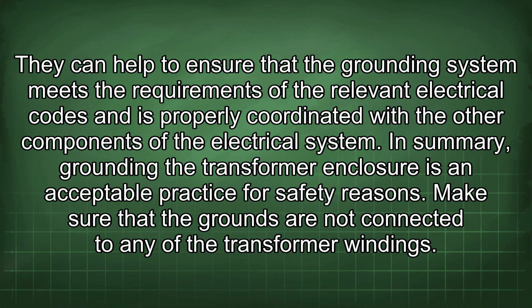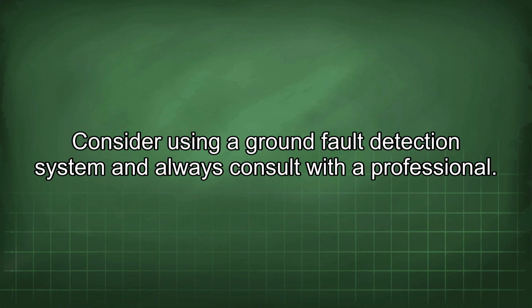In summary, grounding the transformer enclosure is an acceptable practice for safety reasons. Make sure that the grounds are not connected to any of the transformer windings. Consider using a ground fault detection system and always consult with a professional.